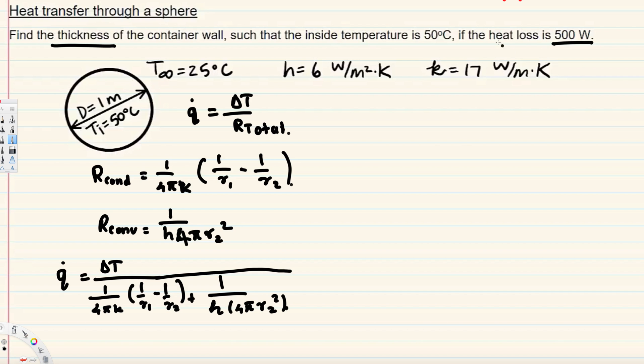We have q-dot which is 500 watts. Delta T is inside temperature minus outside temperature: 50 minus 25, which gives us 25 degrees Celsius, or 25 Kelvin. We have thermal conductivity, and the inner diameter is 1 meter, so inner radius r1 is 0.5 meters. The outer radius r2 is what we are trying to find, because thickness equals r2 minus r1.